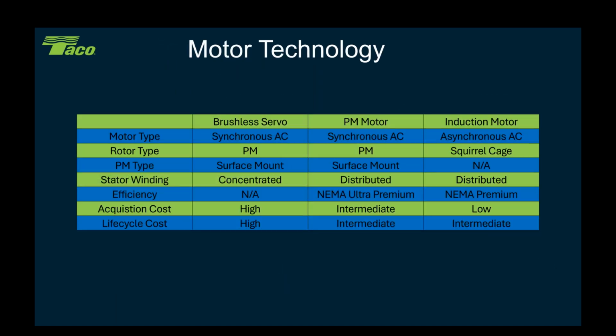So when we look at the different technologies, the biggest thing we've got to understand is that permanent magnet motors and brushless servo motors are both synchronous AC starting, whereas an induction motor is asynchronous starting, okay? What that means is that with asynchronous starting, I can have an across-the-line motor starter, and I can start that motor up by pulling a contactor in, and that motor will start. It doesn't care because it induces the rotating magnetic field into the rotor, so I don't have to get the two magnetic fields lined up to allow that motor to spin. With a permanent magnet or brushless servo motor, I have to get those two magnetic fields lined up before I can allow that motor to rotate. Otherwise, it won't rotate, okay?